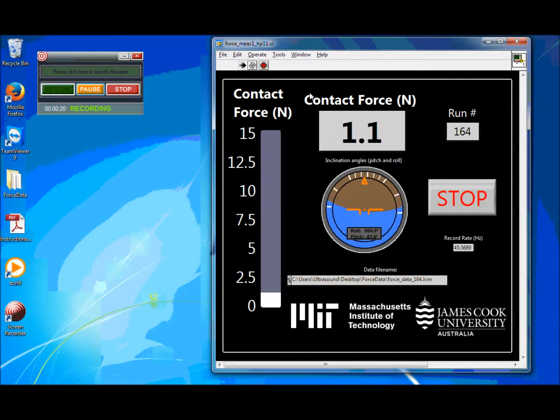So our probe is currently sitting on the table here and is not in contact with anything. And you'll notice that the contact force here still reads a non-zero value. It's about 1 Newton. Now that's probably due to either the way that the cable is velcroed in place, or perhaps the force sensor has warmed up a little bit since we plugged it in. That force that is currently reading is called the bias force. And we want to subtract that out from all the force readings during the exam so that we can get the actual contact force.